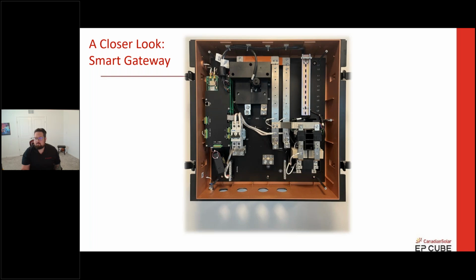Again, the one on the right is intended for EV usage, but our pre-sale support team realized the system doesn't really know if it's an EV charger or a dryer. So if you run a secondary panel off of it, you get that load control Justin was talking about. The system knows that when it's off grid and drops below 60% state of charge, it will kill all those loads—that's what that port allows.